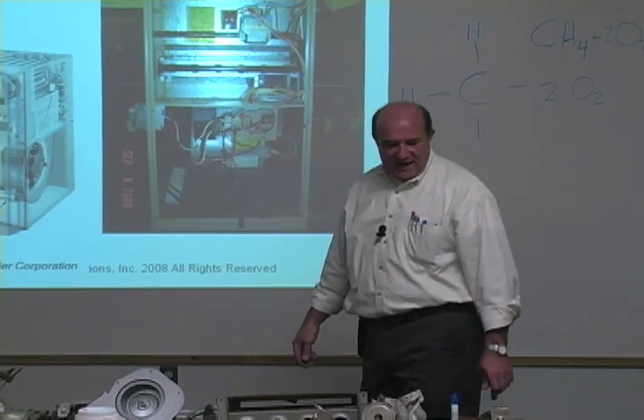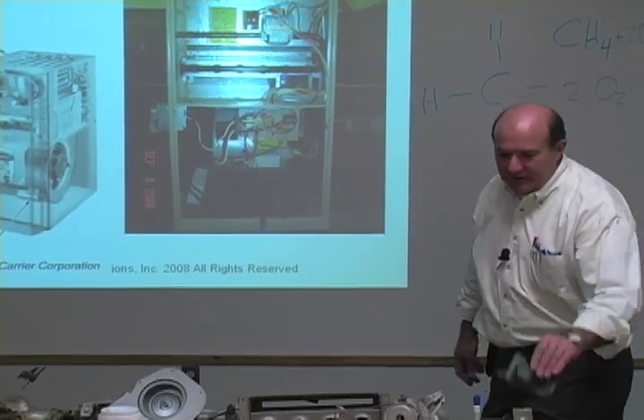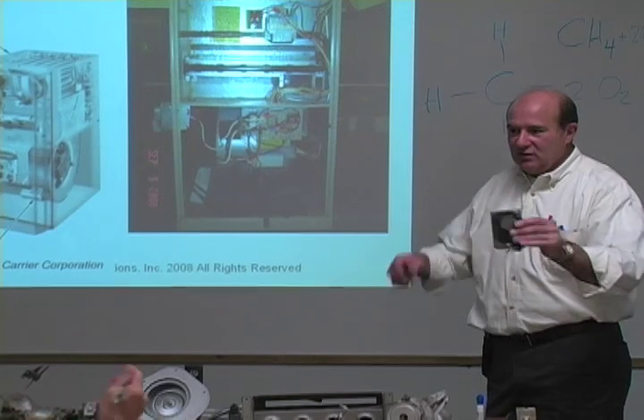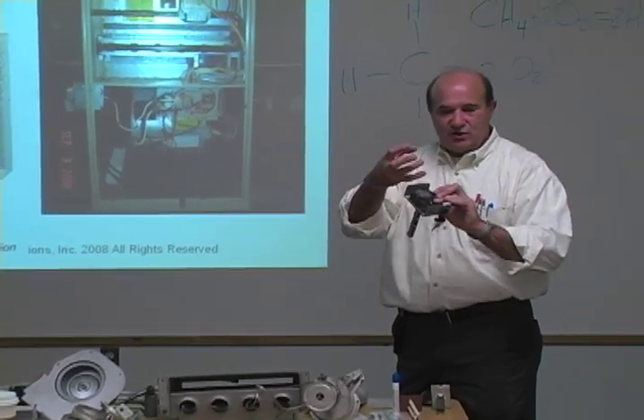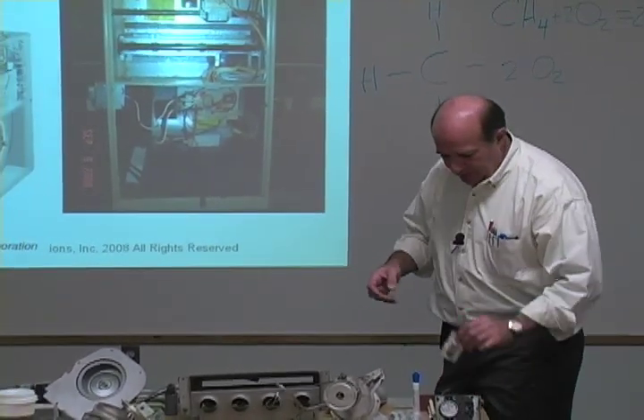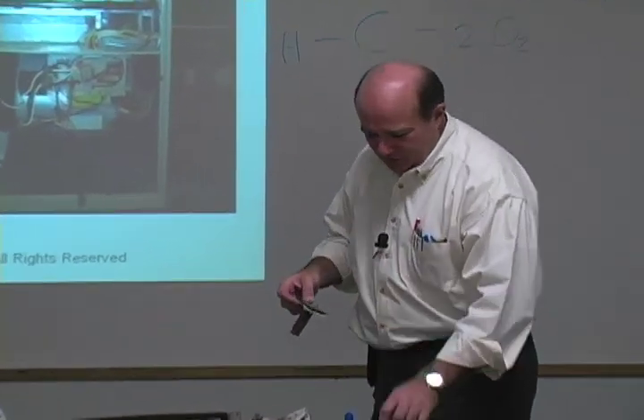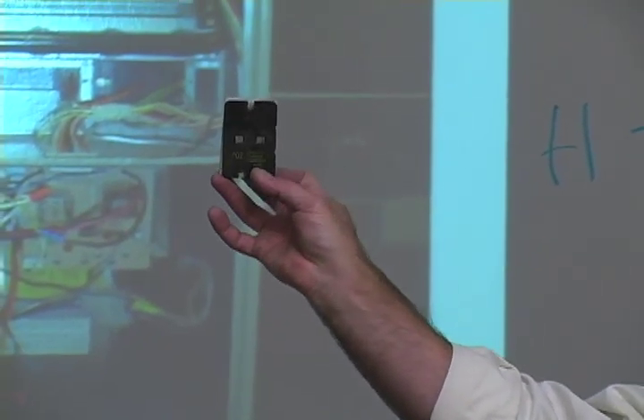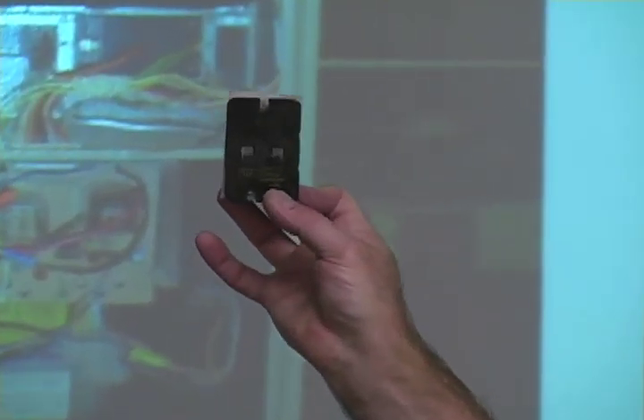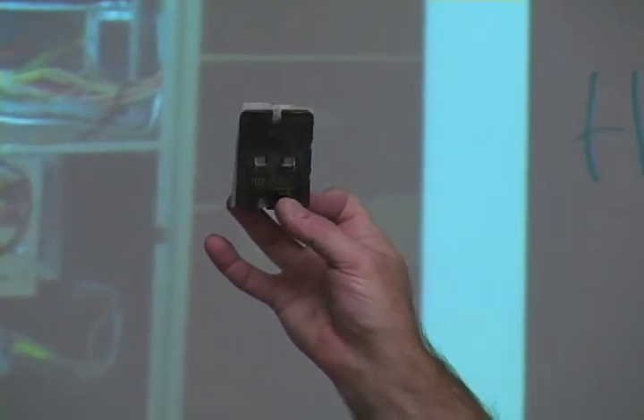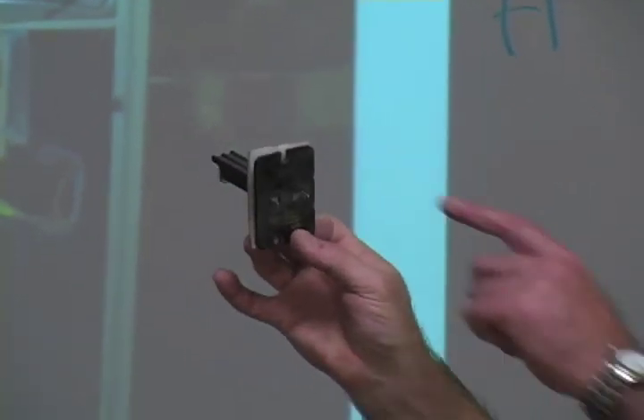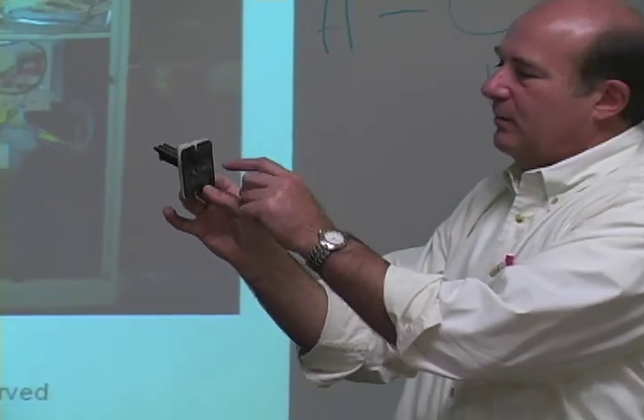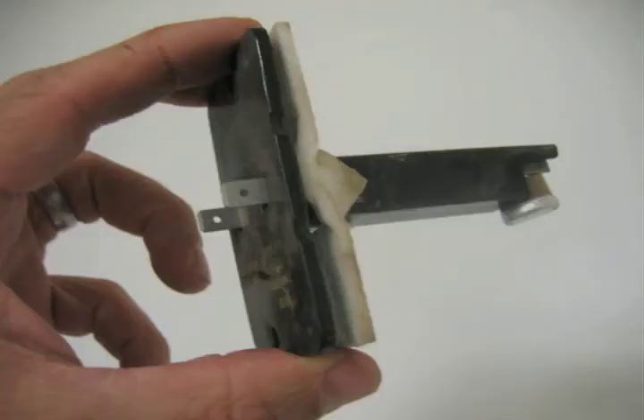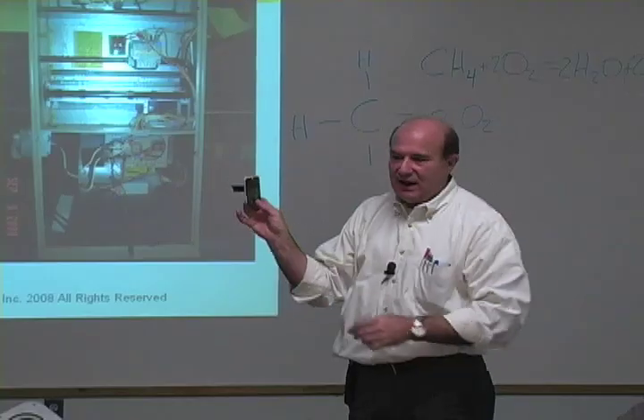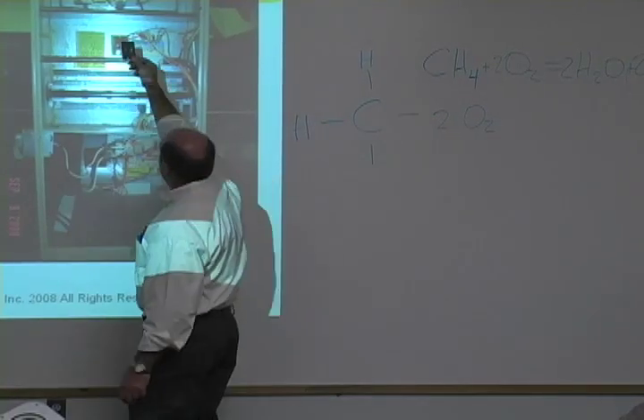Now this furnace doesn't have a mechanical limit switch like this, which causes something to rotate and actually close a switch. It's got this kind of a limit switch in it. Here's two of them. This is a two-prong, normally open, normally closed switch. That means that there's always energy or a complete circuit through this switch at these two. So this is wired in series with our gas valve. You can see on this one, it's located right here on this furnace.